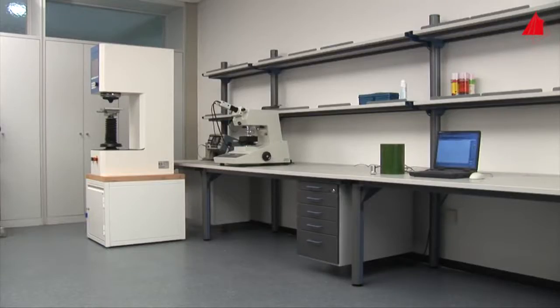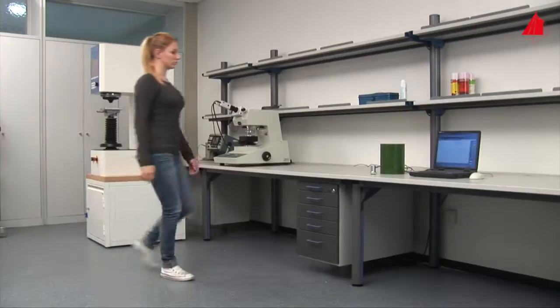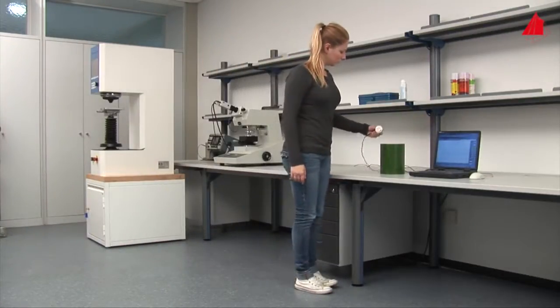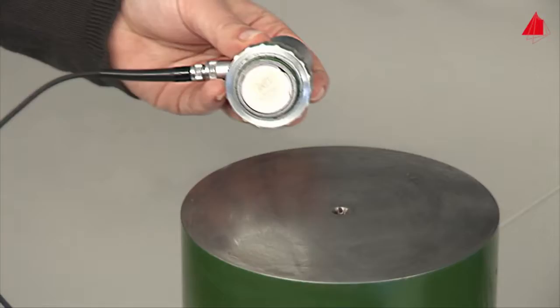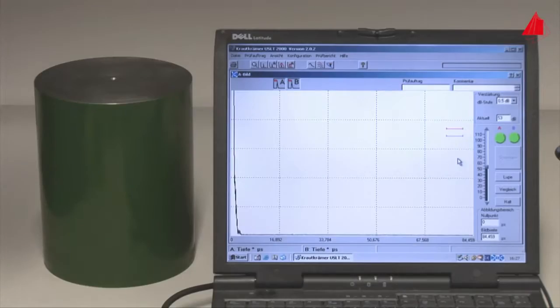In our laboratory, there's a green painted steel cylinder to be found. It contains artificial defects which are invisible from the outside. To track down the defects, the material tester uses the pulse echo method. This is how a typical probe looks like: under the bright wear plate, a piezo electric disc is installed. It can transmit and receive ultrasonic pulses.